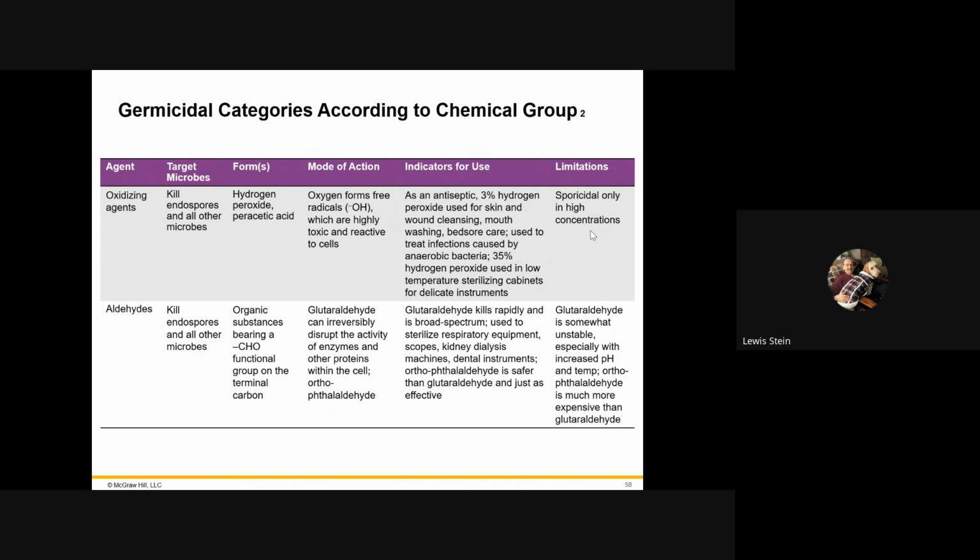You might recall me talking about those suitcase systems that they use for endoscopes, and we call that vapor phase. You might recall me talking just the other day about what they call ultra pasteurization. Those containers have hot vapor phase peroxide used on them, because it evaporates so quickly. It is sporicidal, and it's a remarkable system that allows us to have things like juice boxes, for instance.